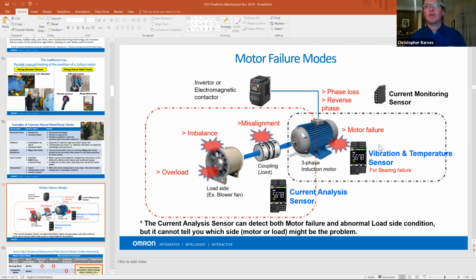I'm thinking of a soft start on a chiller, which has a variable speed drive, because you don't want to shock load it - you have it start slowly at first. If you try to go full speed right away, you've all heard water pumps or air conditioning units that slam on when they don't have a variable speed drive - it starts with a bang, so you can tell there's not a variable speed drive on that.